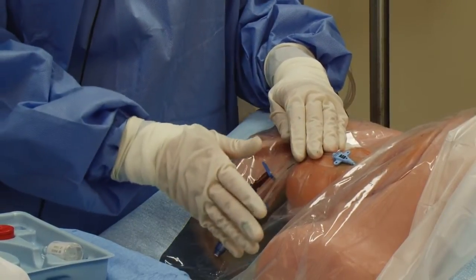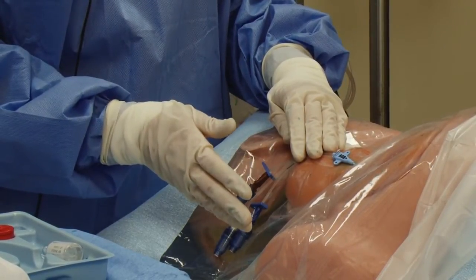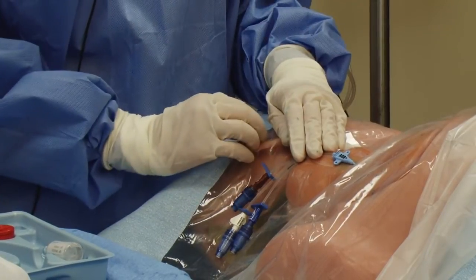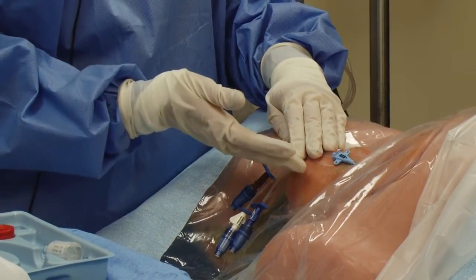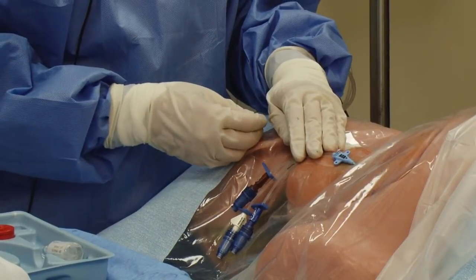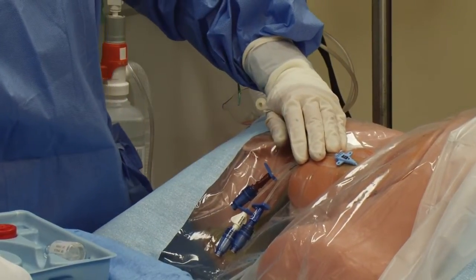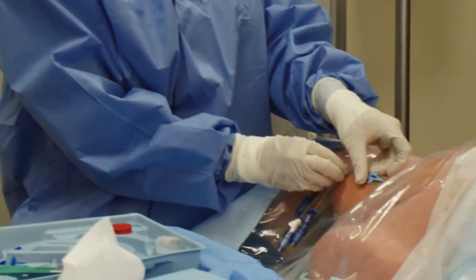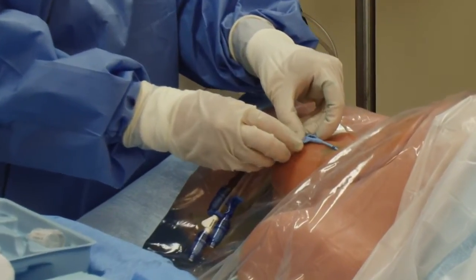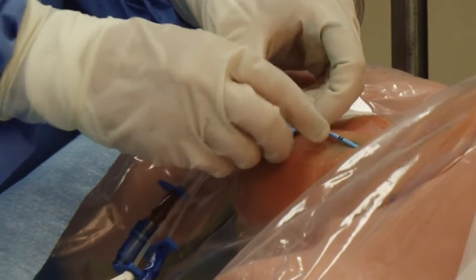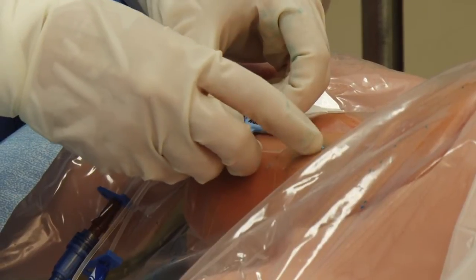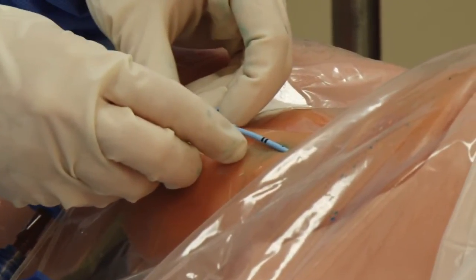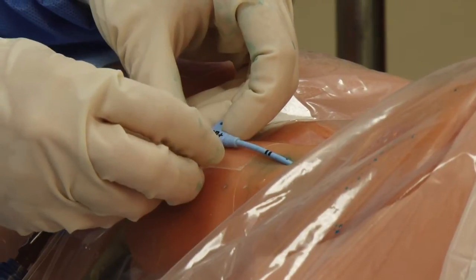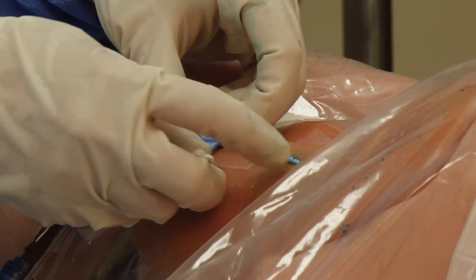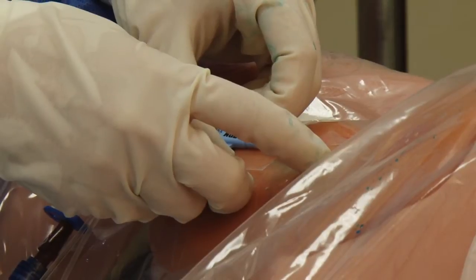Again, on the right side, you should be inserting a 16 centimeter catheter. On the left side, a 20 centimeter catheter. For some patients, a 16 centimeter catheter or a 20 centimeter catheter is going to be too long. If that's the case, that's when you would use these white and blue clamps. You would pull the line out to the desired length, which is measured by two black lines and then black dots. The two black lines represent 20 centimeters on a 20 centimeter and 16 centimeters on a 16 centimeter kit. Each dot further in is 1 centimeter down.